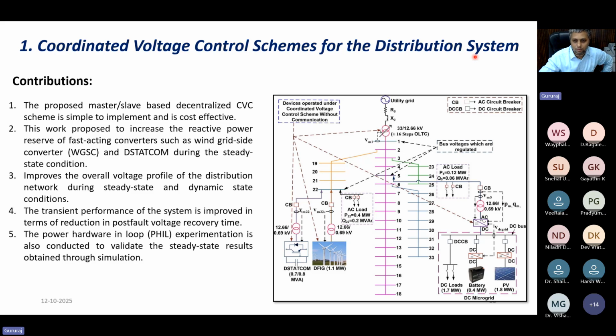So this is the IEEE 33 bus distribution system—it's a radial network. Many renewables are connected: solar photovoltaics and wind are part of the system. Solar photovoltaics through a DC microgrid topology are connected at bus number 5, and there is a doubly-fed induction generator of type 3 wind turbine connected at bus number 22. There is also a DStatCom connected close to the same vicinity to support the DFIG during fault ride-through, and an on-load tap changing transformer at bus number 1.